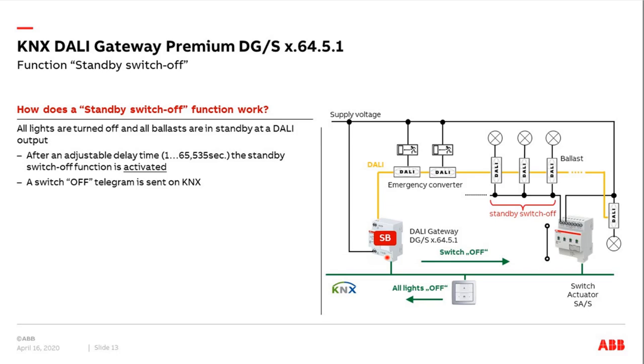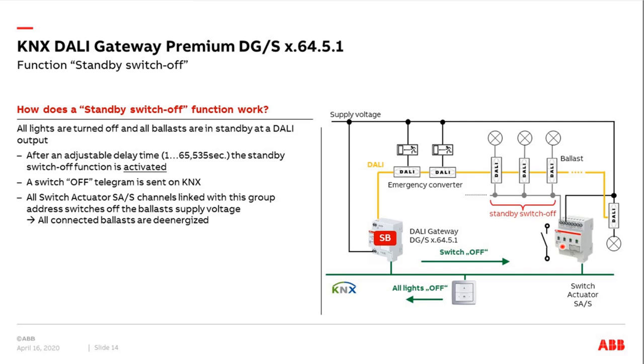The DALI gateway sends a KNX telegram with the logical value zero to the KNX bus. The switch actuator channels linked to this group address receive the telegram and switch off, opening the relay. The supply voltage for all ballasts is now switched off and the ballasts are de-energized. Normally the DALI gateway would send a ballast fault message because it cannot reach the ballasts, but during the standby function the gateway sends no ballast fault message to KNX. During the night, the DALI ballasts are fully de-energized.